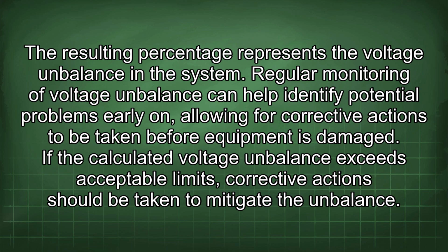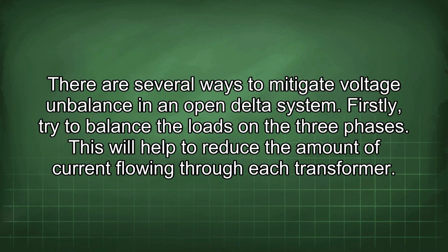Regular monitoring of voltage imbalance can help identify potential problems early on, allowing for corrective actions to be taken before equipment is damaged. If the calculated voltage imbalance exceeds acceptable limits, corrective actions should be taken to mitigate the imbalance. There are several ways to mitigate voltage imbalance in an open delta system. Firstly, try to balance the loads in the three phases. This will help to reduce the amount of current flowing through each transformer.